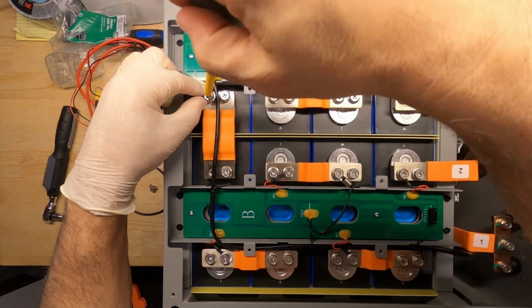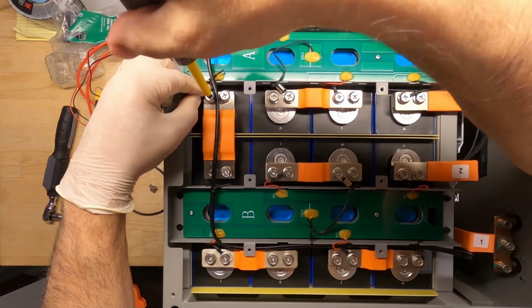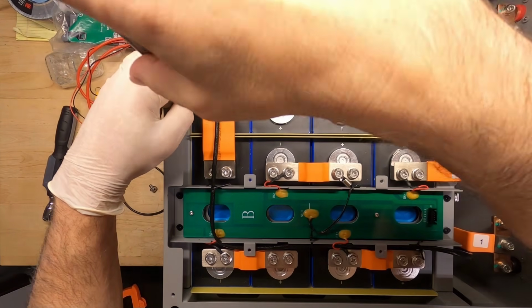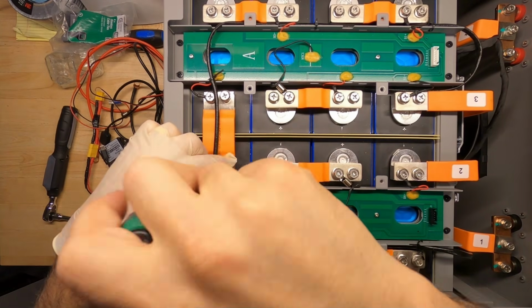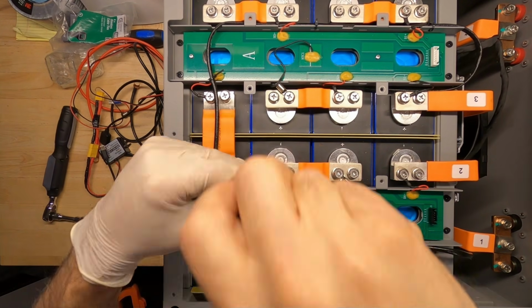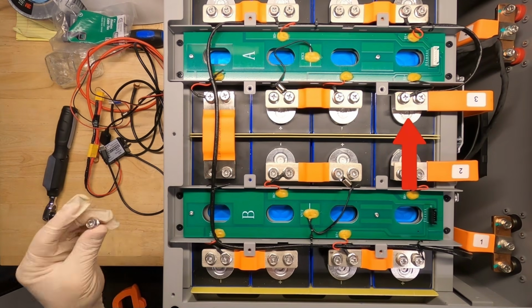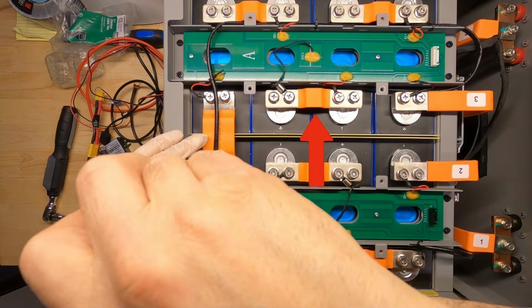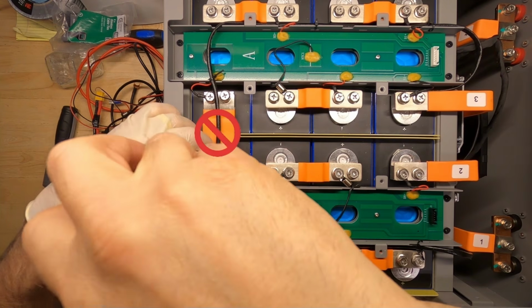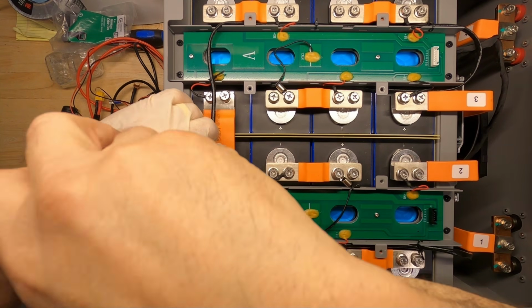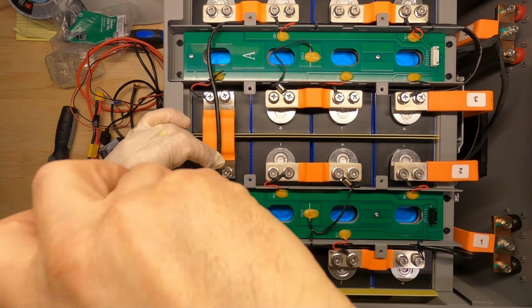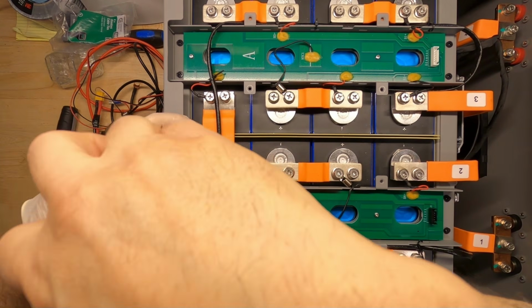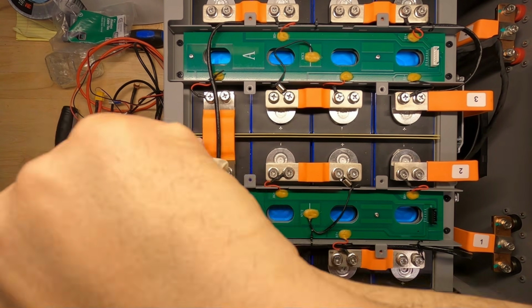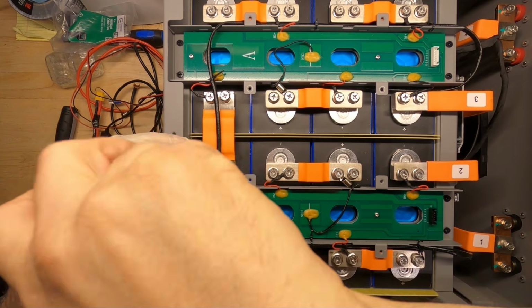Now the pack is energized, 24 volts, so just keep that in mind. Now, if you're using single stud cells, the bridge bus bar will not work. The mains up here and all the connecting ones will work on single cell studs, but this one will not. You'll have to use a jumper cable. We got to get them to start sending 2 bus bar types, or make a universal one.